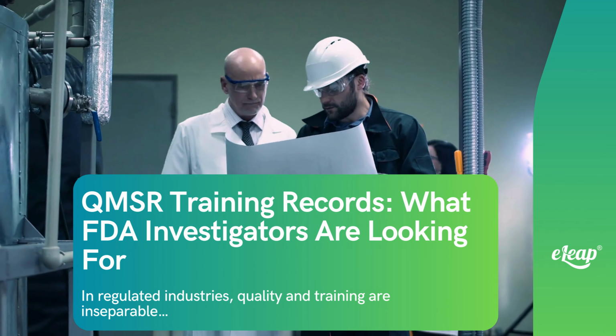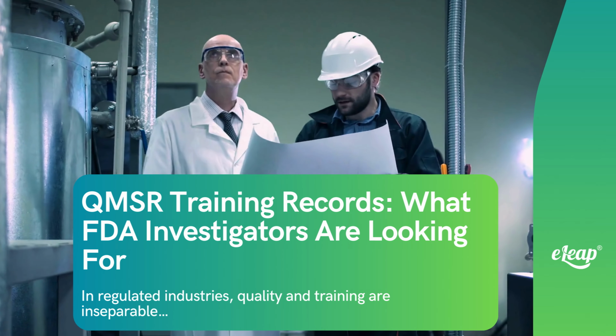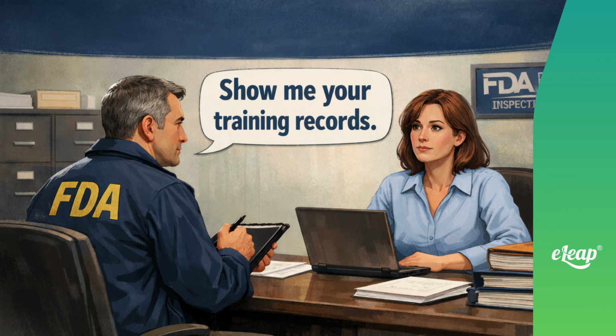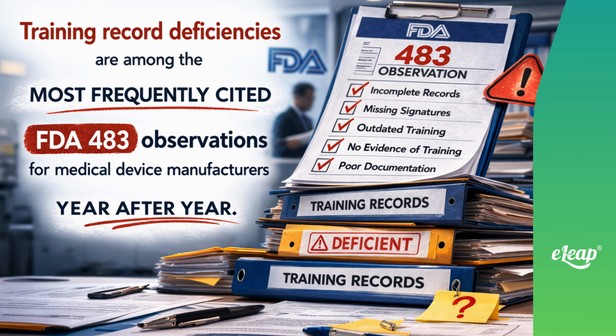An FDA investigator sits across from your quality manager and makes a single request: show me your training records. What happens next determines whether you walk away from that inspection with observations or a warning letter. Training record deficiencies are among the most frequently cited FDA 483 observations for medical device manufacturers year after year, under the previous quality system regulation and under the QMSR that replaced it in February 2026.